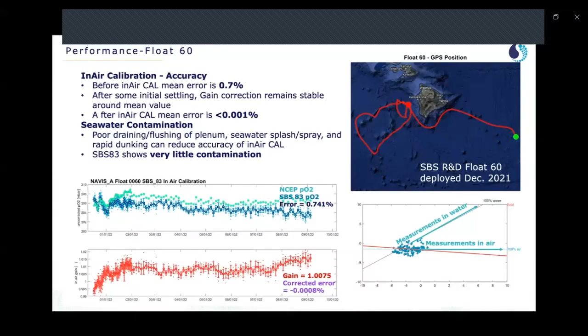And seawater contamination is caused by poor draining or flushing of the plenum, seawater splash or spray, and rapid dunking of the sensor, which reduces the accuracy of the in-air cal. If you look in the right-hand corner, you'll see the diagonal line is an indication of measurements taken in the water versus the horizontal line, which are measurements taken in the air. And the red line that you see there is the least square of all of the data taken on float 60. And if you compare the in-air measurements to the red line, you can see that it's very close to almost taking all of its measurements in air, which means that there's very little seawater contamination with this particular float.